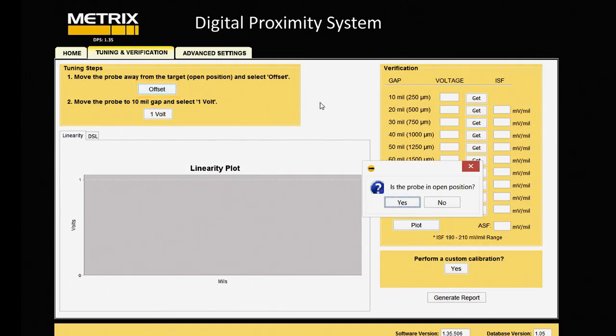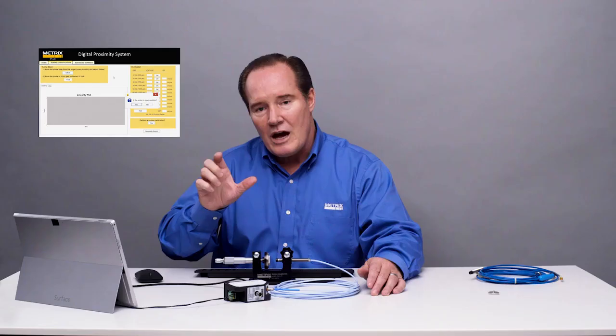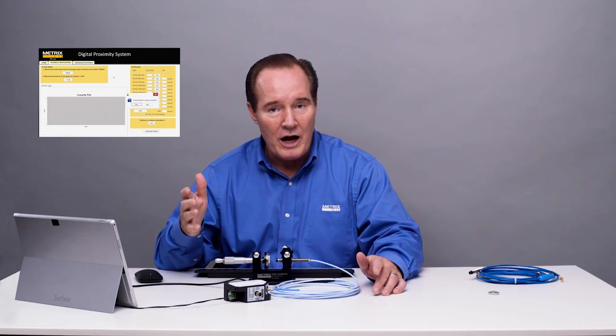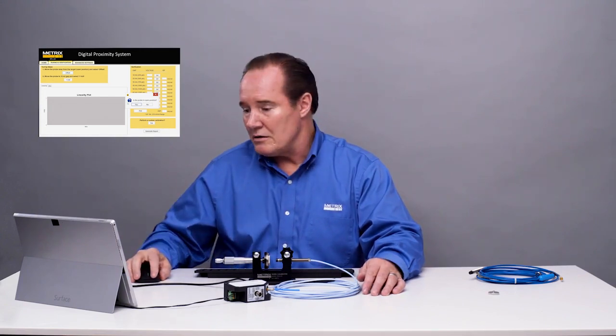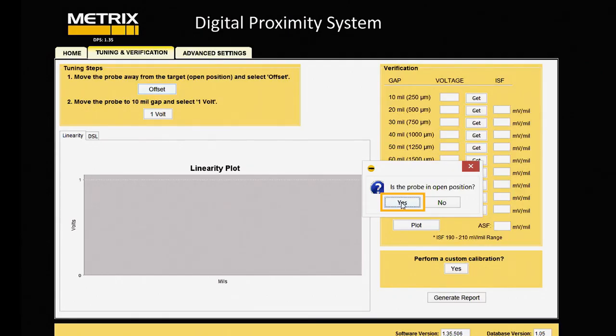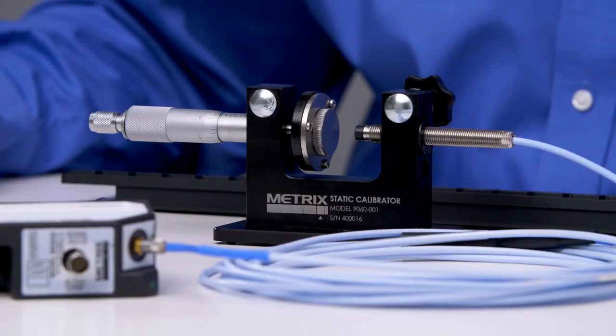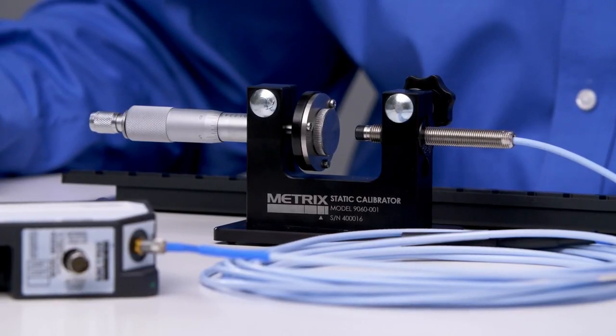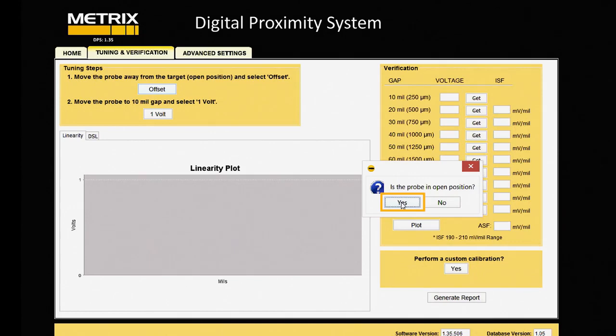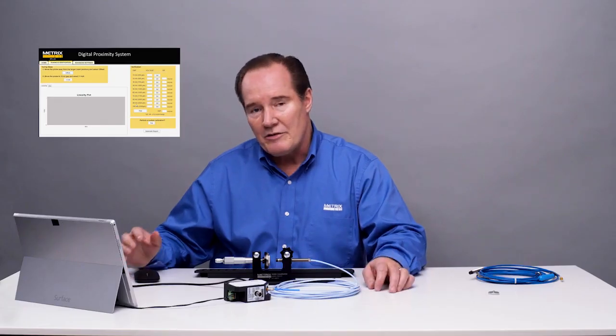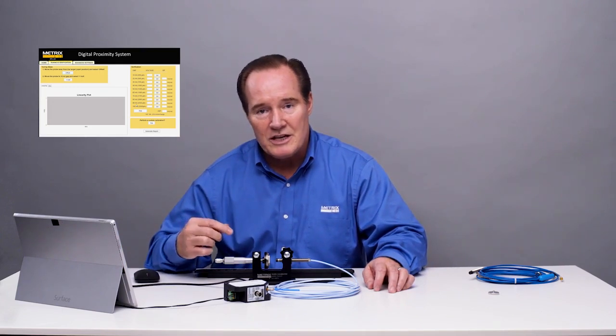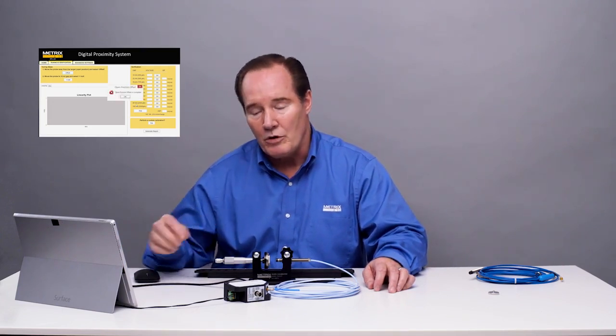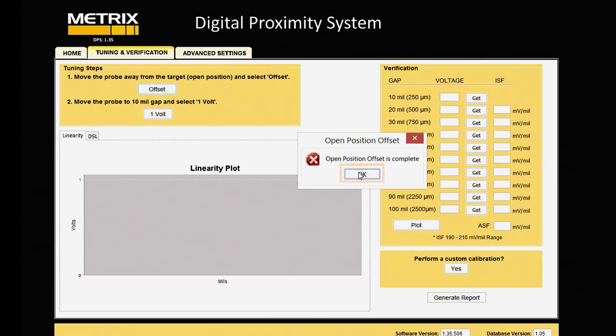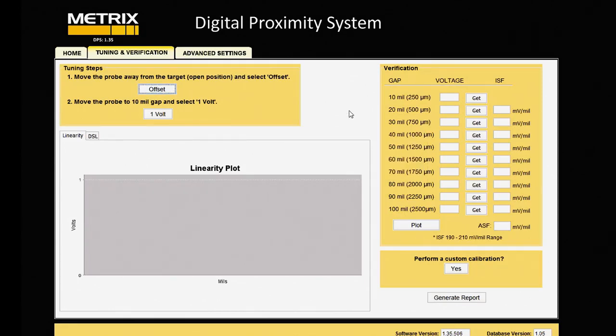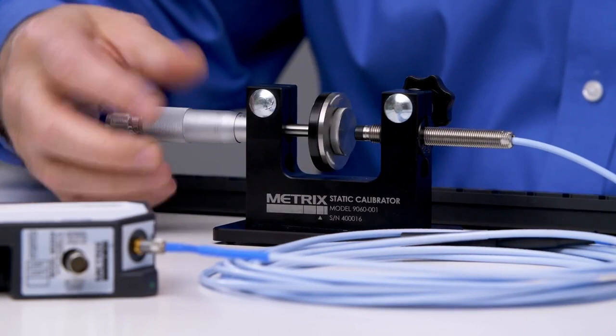Offset gets the top end of our curve when we look at the scale factor on our plot. And we'll say, is the probe in the open position? It is. There's more than a half an inch of gap there, which is what we need, over 12 millimeters. Make sure we don't have any influence, and we'll say yes. And now we'll record that data. Then we'll have me move the dial micrometer to 10 mils gap, and then we'll get it at 1 volt. Okay, offset is complete. Now we'll go to 10 mils at 1 volt.